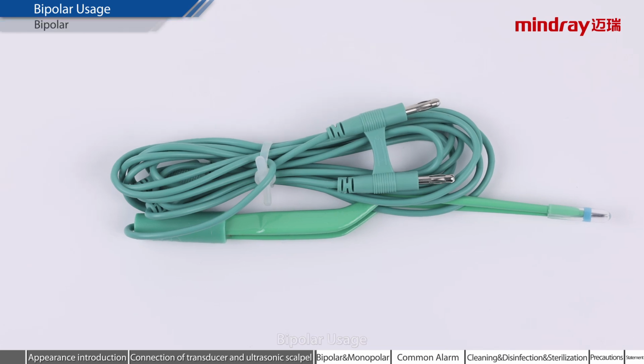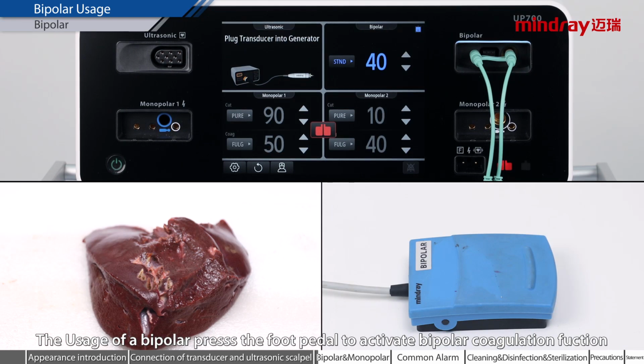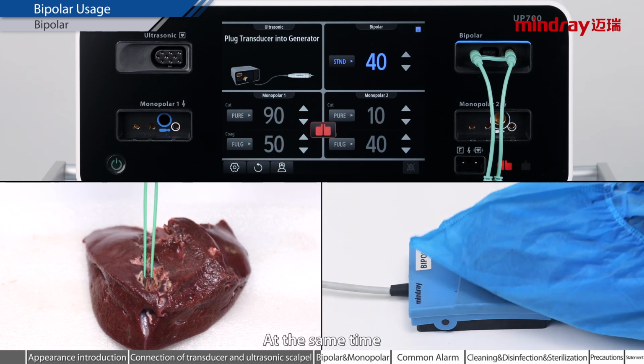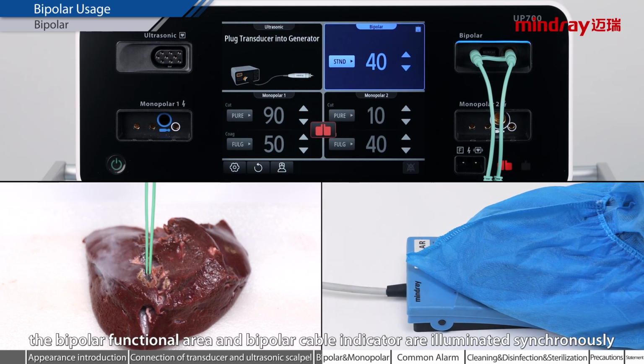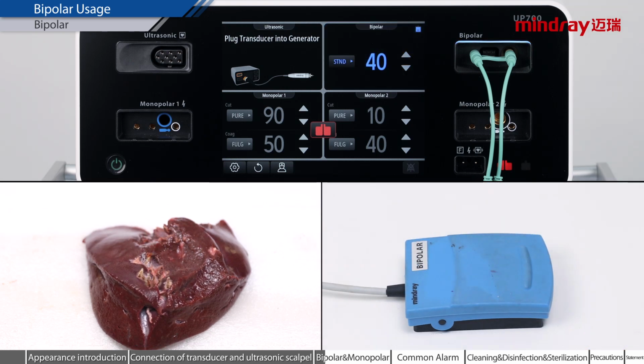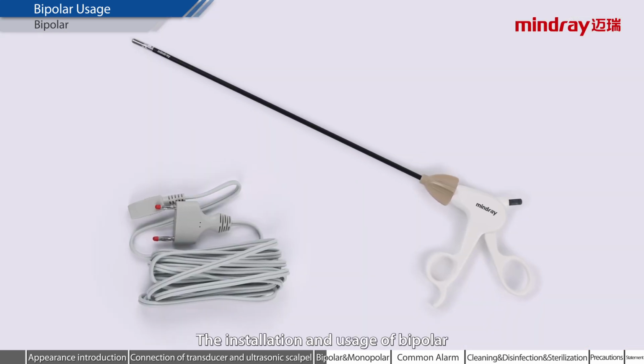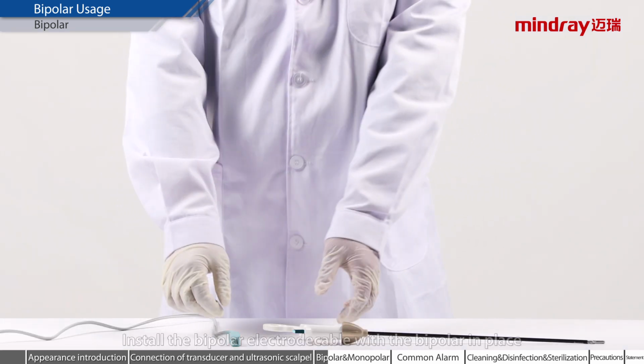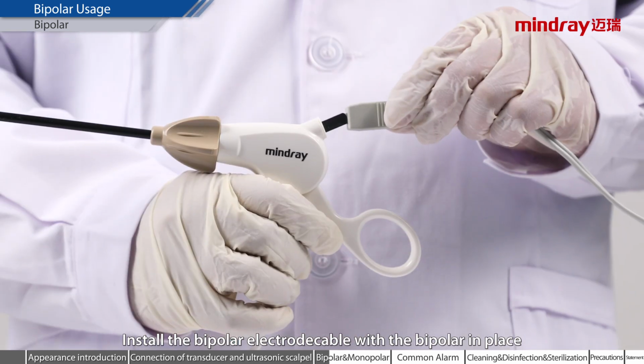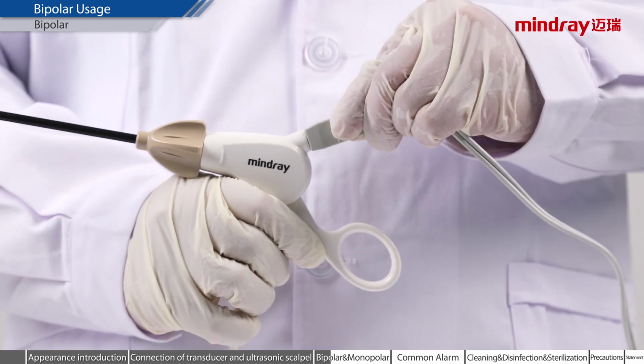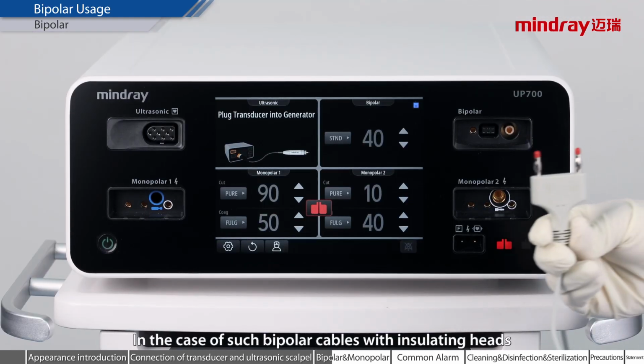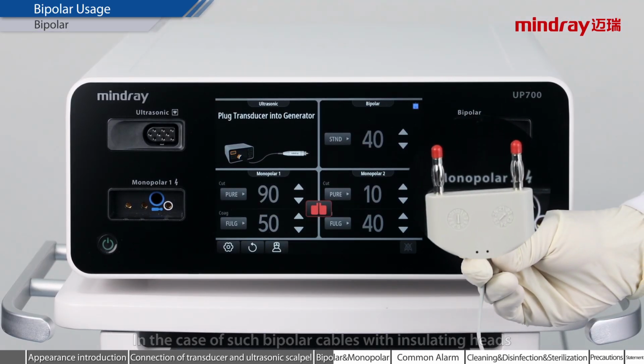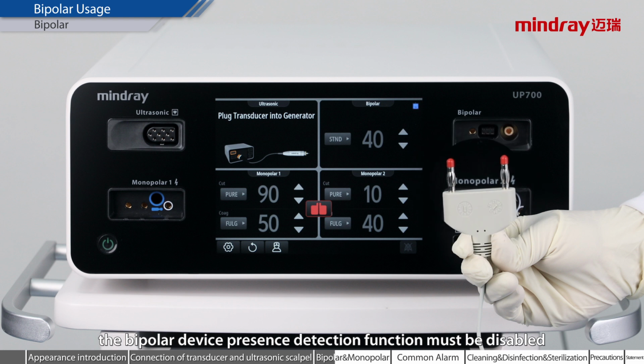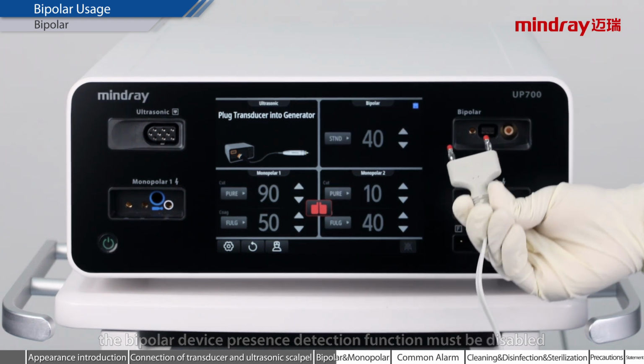Bipolar usage. To use the bipolar, press the foot pedal to activate the bipolar coagulation function. At the same time, the bipolar functional area and bipolar cable indicator are illuminated synchronously. The installation and usage of bipolar. Install the bipolar electrode cable with the bipolar in place. In the case of such bipolar cables with insulating heads, the bipolar device presence detection function must be disabled.